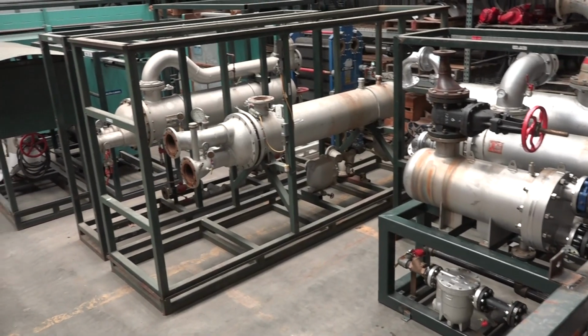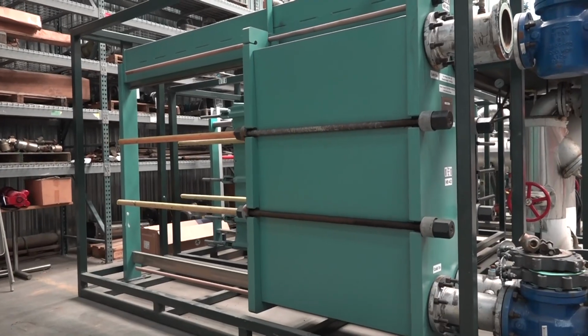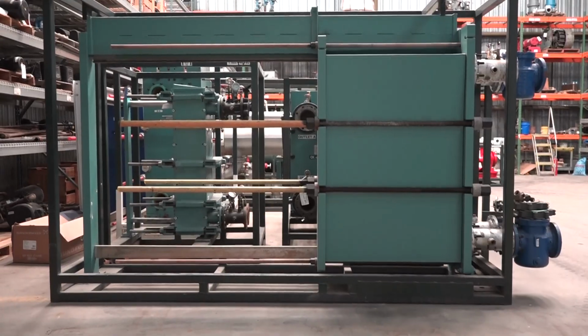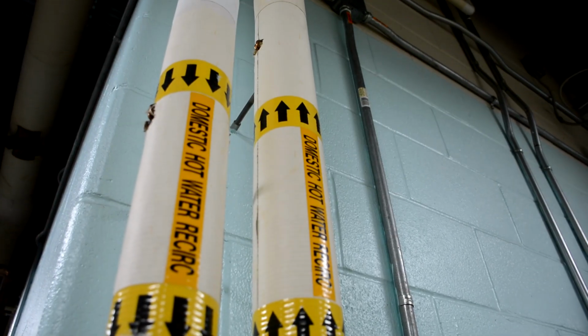A plant with an installed steam boiler that needs hot water, whether for heating or domestic purposes, could utilize a heat exchanger sized accordingly to meet the hot water demand. Now this would allow the system to have its steam load delivering for various other operations, whether it's heating, sterilization, or process needs, and still provide the hot water without having a separate hot water boiler.